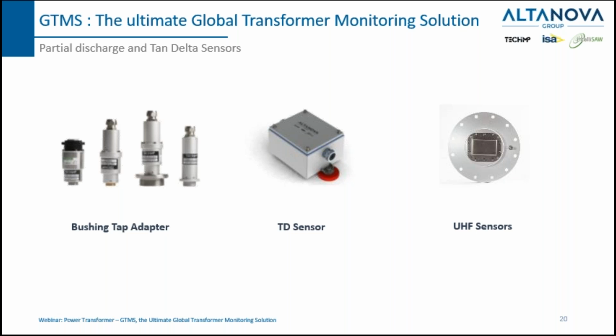In terms of sensors and accessories, you can have here a very easy example of the most important components of the system. Here, the bushing tap adapter. A tap adapter connects to the test tap of the transformer bushing and is suitable also for partial discharge measurement and for tan delta measurements. This tan delta sensor is the component that we use normally for tan delta measurement. And these are connected to the bushing tap adapter up to the EDS unit. And on the right, an example of a UHF sensor that we use in this case connected directly to the tank of the transformer.